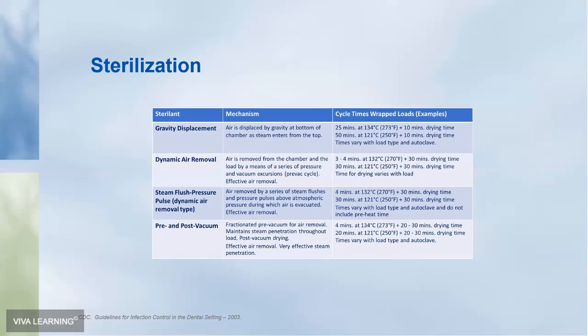I'm not going to go through this table, but as you can see, there are several methods of sterilization. Gravity displacement, as the name suggests, the air is displaced by gravity at the bottom of the chamber. The others all involve pre-vac cycles, and the pre and post-vacuum includes a post-vacuum cycle, which provides post-vacuum drying. The times vary. You have to add on the drying times, and it depends on the type of device, and it depends on the temperature that was used.